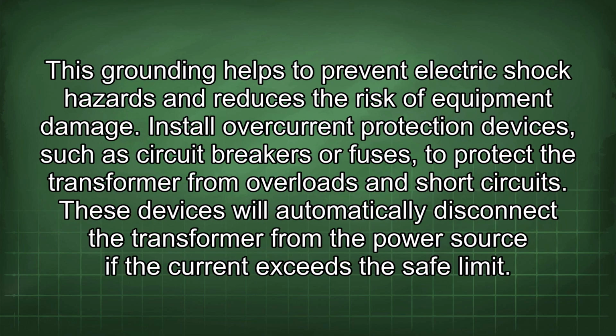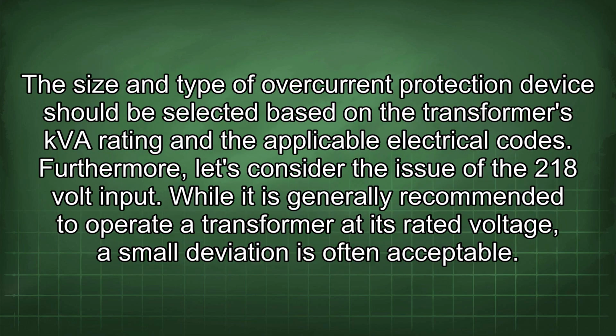This grounding helps to prevent electric shock hazards and reduces the risk of equipment damage. Install overcurrent protection devices, such as circuit breakers or fuses, to protect the transformer from overloads and short circuits. These devices will automatically disconnect the transformer from the power source if the current exceeds the safe limit. The size and type of overcurrent protection device should be selected based on the transformer's kVA rating and the applicable electrical codes. Furthermore, let's consider the issue of the 218-volt input.